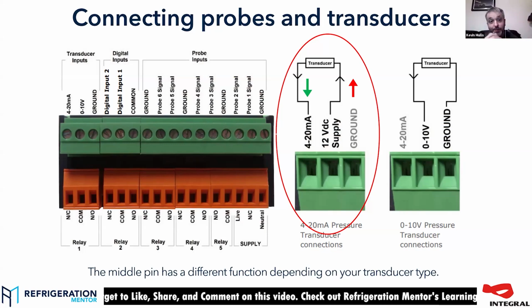One thing worth bearing in mind with RDM is that if the transducer goes into fault, it will default back to using probe 3 for your inlet temperature, for your evaporating temperature effectively. So you do need to fit probe 3, which is the coil inlet probe, regardless of whether you're using a transducer or not. Otherwise, it will flag a fault, and it's not going to work. It is not going to work if the transducer goes away.